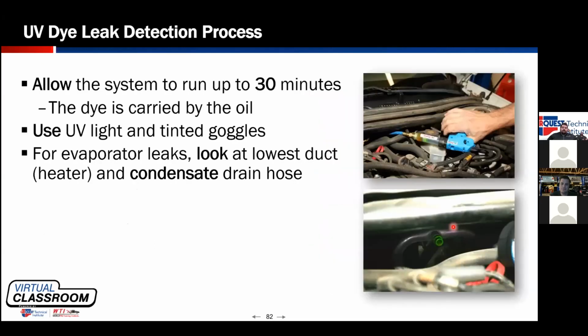As we said, you have to circulate the dye. Sometimes if you have an evaporator leak, either using an inspection camera with a UV tip on the end of it, you might be able to see dye on the surface of the core. You might be able to see some dye in the drain water or at the end of the drain hose. Use the light that works with your dye. Use the goggles if necessary.